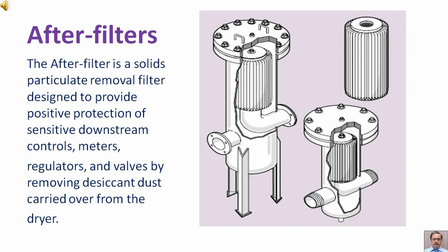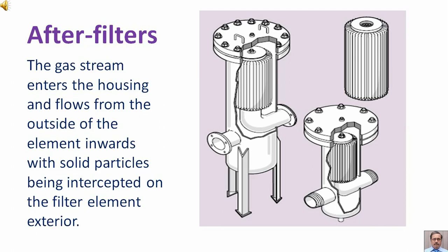The after-filter is a solid particulate removal filter designed to provide positive protection of sensitive downstream controls, meters, regulators, and valves by removing desiccant dust carried over from the dryer. The gas stream enters the housing from the outside of the element inwards, with solid particles being intercepted on the filter element exterior.